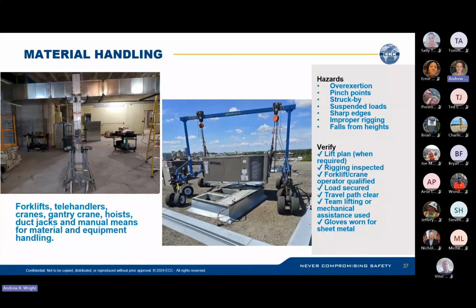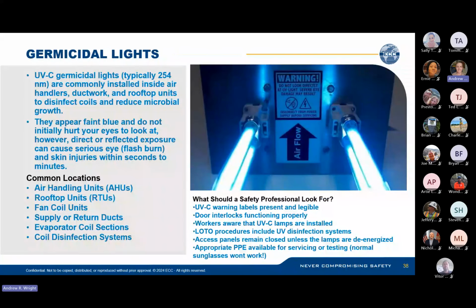Germicidal lights. These are UVC lights, typically installed in air handlers, ductwork, and rooftop units. They disinfect coils and reduce microbial growth. They appear faint and blue. They don't initially hurt your eyes to look at because UVC is not really in the visible light spectrum. So it's not like looking at the sun, where it's very bright and you'll look away. You can look right at these things. So you may not know, if there's not a warning sign on it, that you can't look at these.